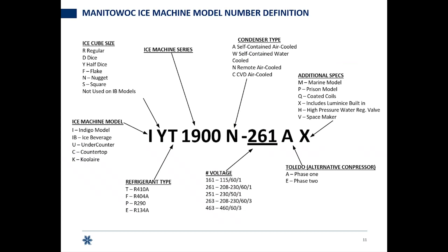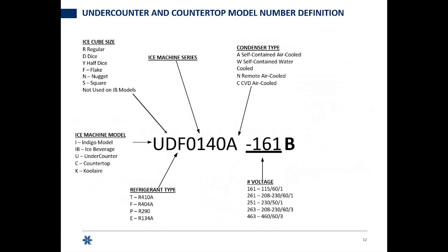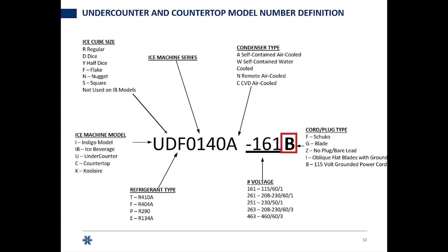And there's the whole model number definition again on the screen, letting you see what we're calling out. We do want to highlight the undercounter series just a little bit. Everything up through the electrical code is going to be the same, but there's going to be a letter at the end of the electrical code — and it's not for an alternative compressor. Our undercounter series have a cord that comes with them, and it designates the cord/plug type. This one has a B as in Bravo, letting you know it's a 115-volt grounded power cord. Our modular units do not come with cords installed from the factory — that will have to be installed upon initial install by a qualified technician.